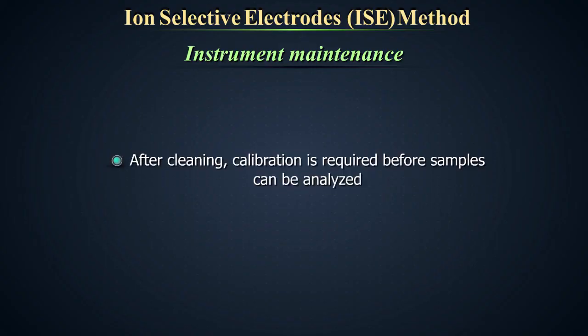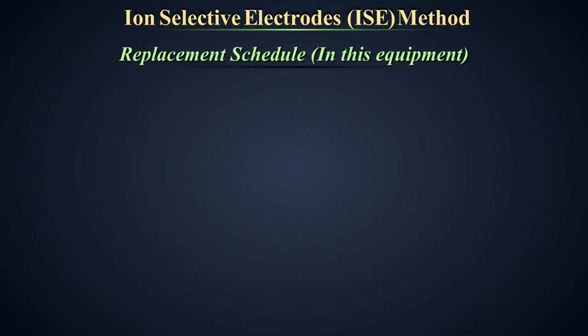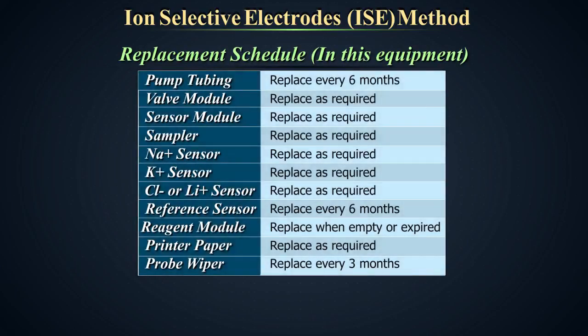After cleaning, calibration is required before samples can be analyzed. This instrument performs an automatic calibration and is then ready to analyze samples. Replacement schedule. The following schedule should be followed. Out of these, pump tubing, sensors, reagent, and printer paper can be done by the technician. The rest should only be performed by the service person or engineer.